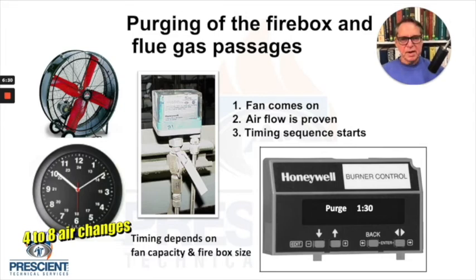Where do you get fan capacity? Well, from fan curves, from measuring amps on fans, but it's generally good to actually measure that airflow in practice in the field to know that you're getting what you expected to be getting. So on the burner management system display, if it's a Honeywell 7800 series like I'm showing you here on the inset, there should be a purge timer and a purge time indicated and a purge time countdown.